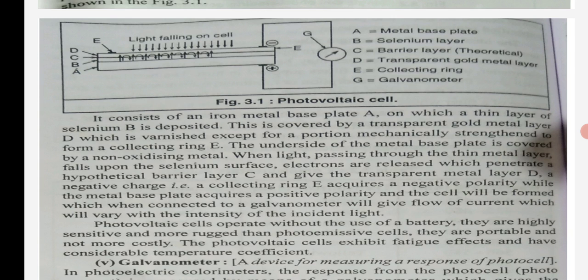The source of light is transmitted through a collimating lens and then to a filter and a movable holder containing the reaction cell or cuvette, and then to the photocells. The photocells transmit to the galvanometer, and the galvanometer records the optical density.